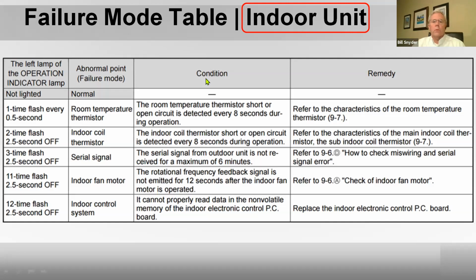Make sure that when you download the service information, you know what unit you're looking at, because on the indoor head, it may have a flash code. Right down where the receiver is, there's some lights we talked about earlier, and that light will flash a code. In this case, it says 2-time flash, 2.5 seconds off, and then flash twice, and 2.5 seconds off, and flash twice. That's a 2 flash. That means you've got an indoor coil thermistor bad on this particular unit we're looking at, which is an indoor unit.